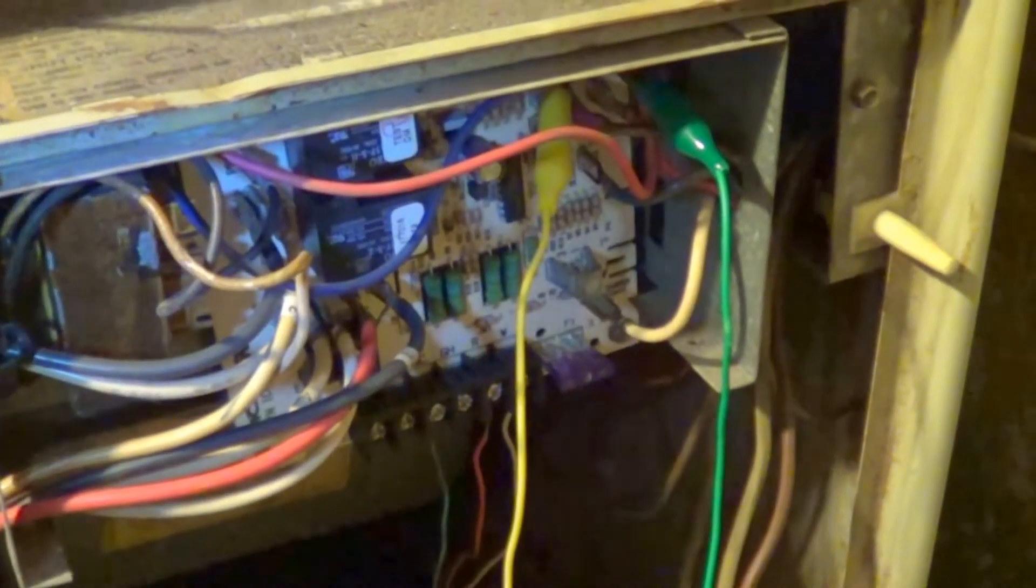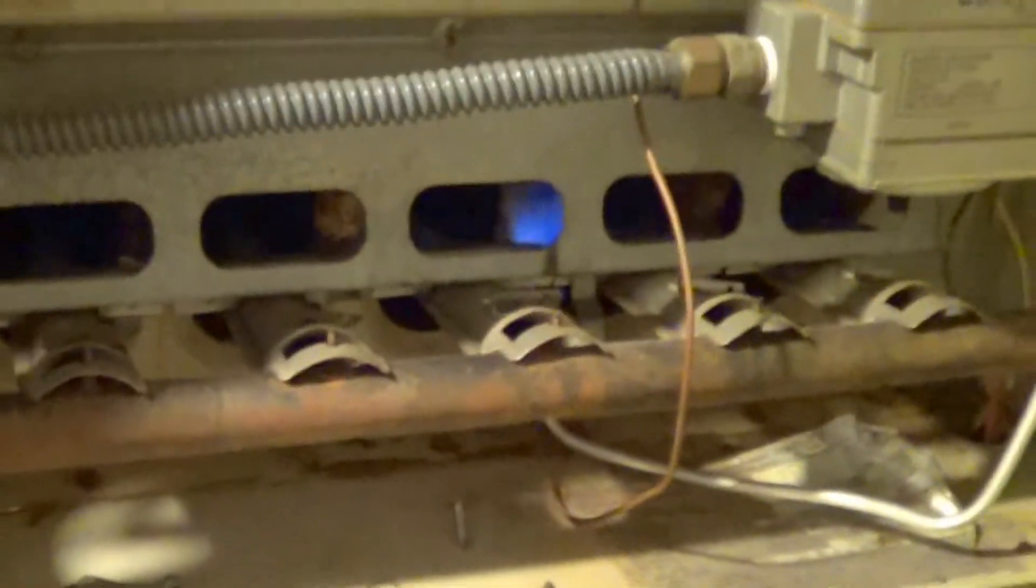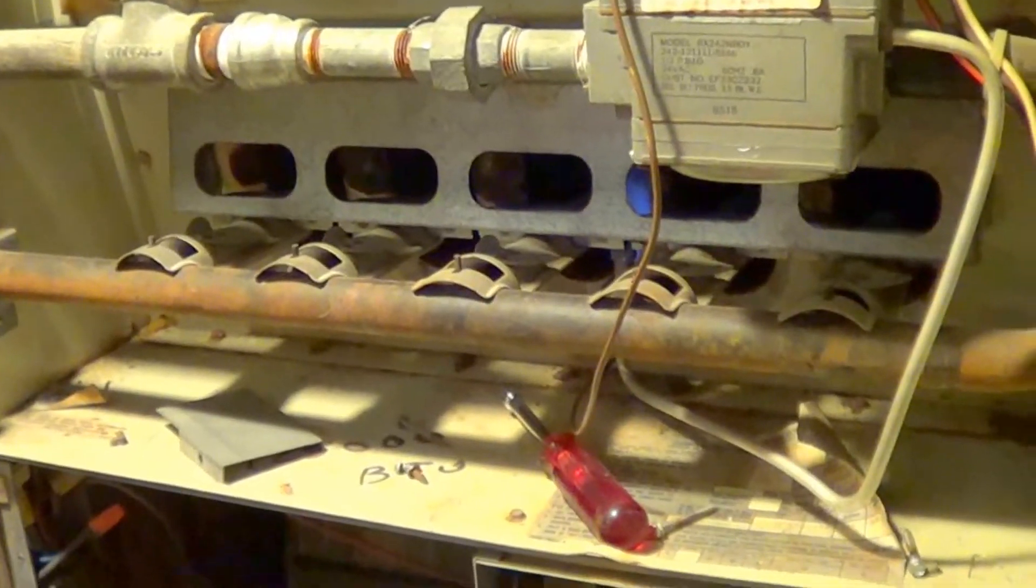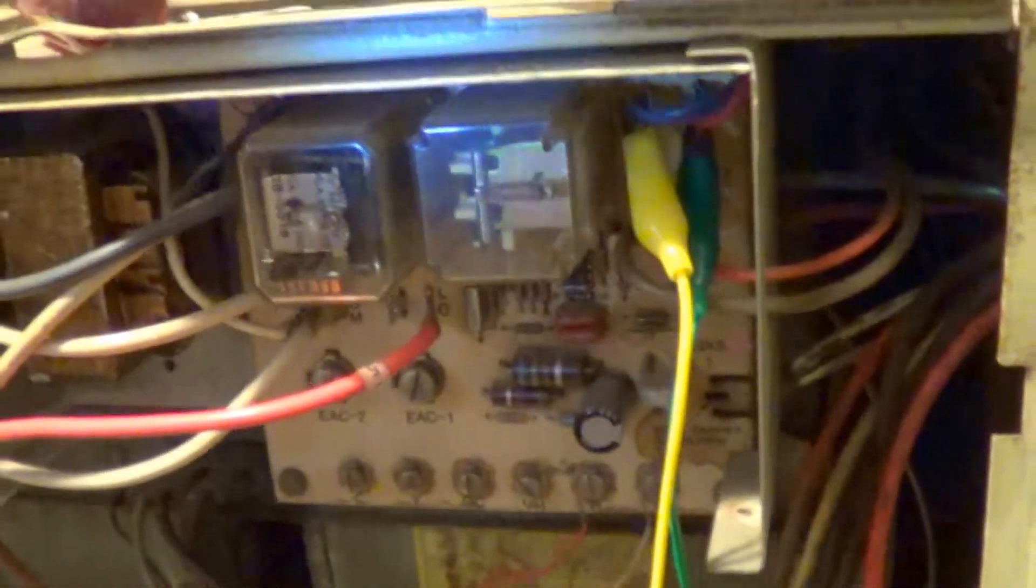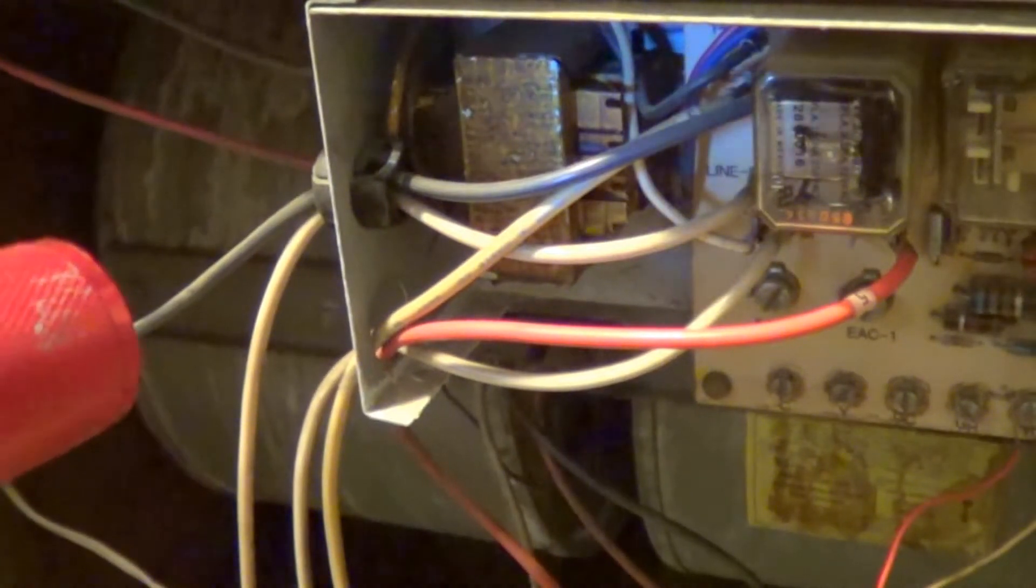On the right control board I've got 28 volts here on the output of the control transformer. That's the control board, that's the right furnace. There's the left furnace. Now we're going to check this control board. On the left control board there's the control transformer. Got no voltage across it on the output of the transformer. Now I'm going to check the input to the transformer. 110 volts on that one.